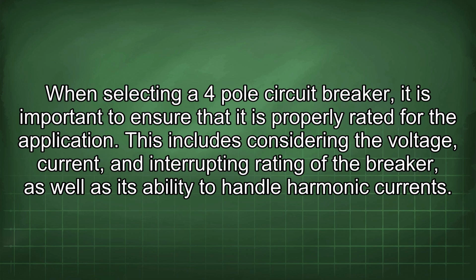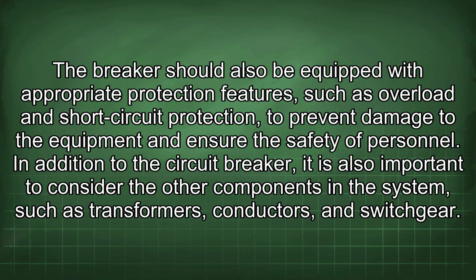This includes considering the voltage, current, and interrupting rating of the breaker, as well as its ability to handle harmonic currents. The breaker should also be equipped with appropriate protection features such as overload and short circuit protection to prevent damage to the equipment and ensure the safety of personnel.